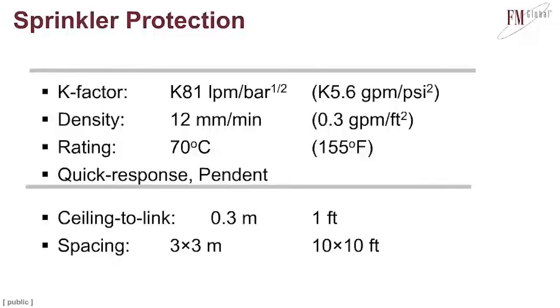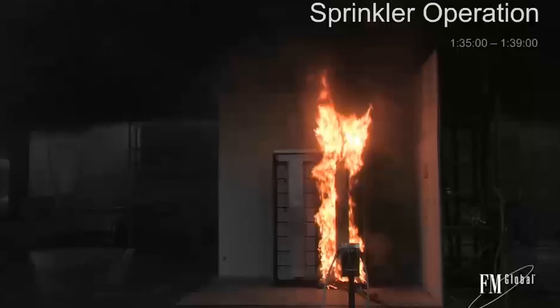The reason I went with that approach is that these are the only large-scale tests that I'm aware of that are publicly available. So there's not a lot of information for us to fall back on to develop our knowledge of protection effectiveness. If I were to find out that you needed a 1.0 gallon per minute per square foot density, does that really have a lot of relevance if facilities aren't willing to put that much water in? So we went with the standard 0.3 density with K5.6 sprinklers, ordinary temperature, on normal spacing. What I'll show you here in a minute is what the sprinkler operation looks like.